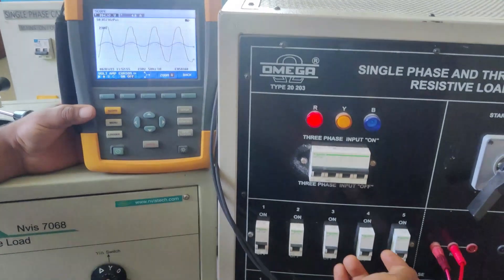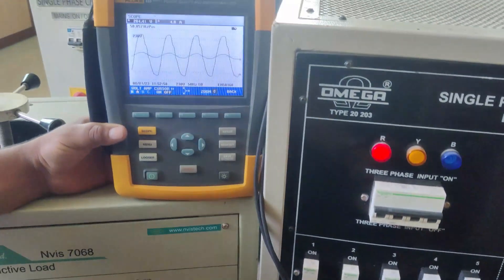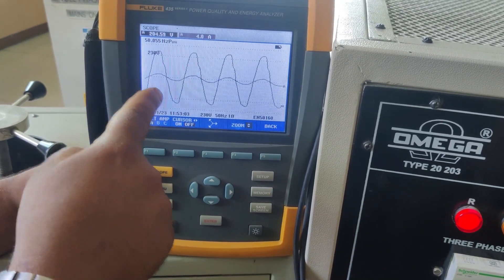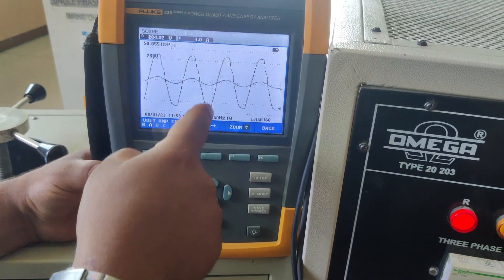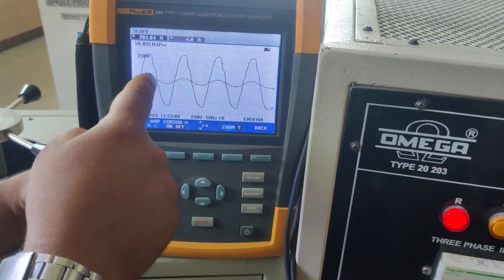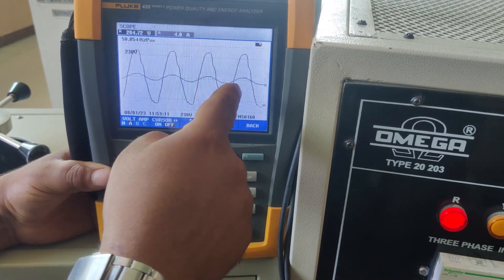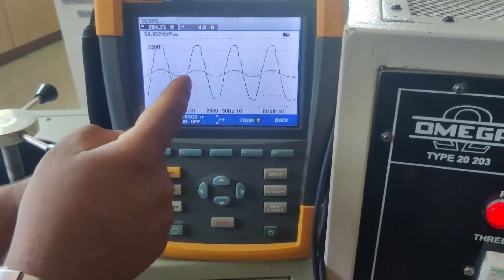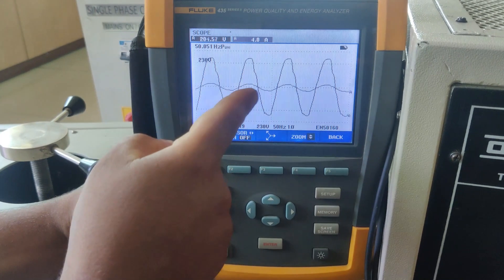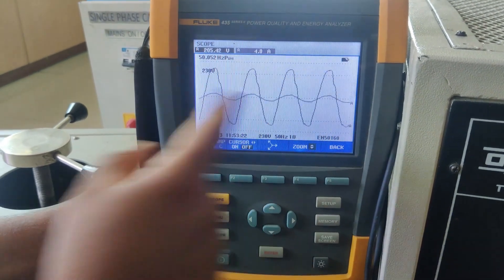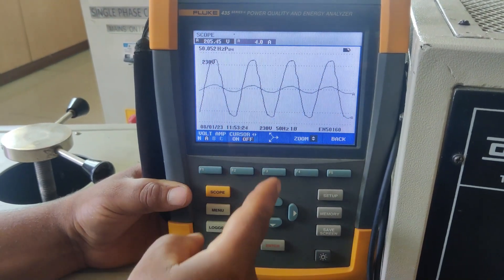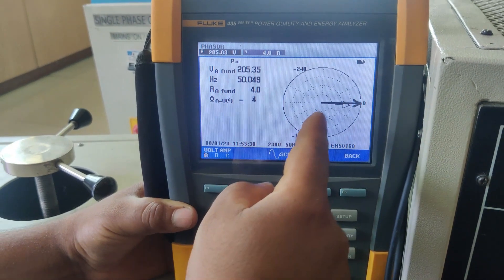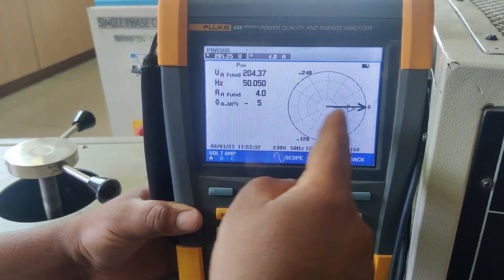As I have turned all 4 MCBs on for this phase, you can see the current is 4 amps. In the time domain representation, the larger waveform is the voltage and the smaller one represents the load current. You can analyze that the voltage and current are in phase — the positive and negative cycles align with no phase difference. On the phasor representation, the voltage is the bigger phasor and the current is the smaller phasor, and they are in phase.